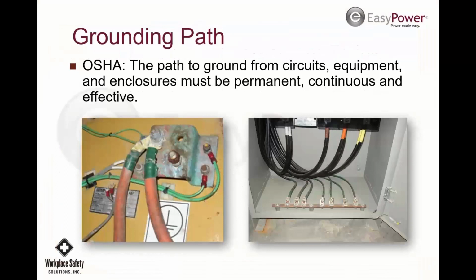Grounding is really important. So you have grounds like this that are very high resistance. It's going to have an impact on the time current curve of the breaker, because a breaker has to see the fault. It has to have reference to ground to see that fault. And if it doesn't, if it's got a high impedance fault, it's not going to trip the breaker the way it should. It's going to take a lot more time, which then can cause more ionization and more likelihood of failure. So you want to have good grounding connections.